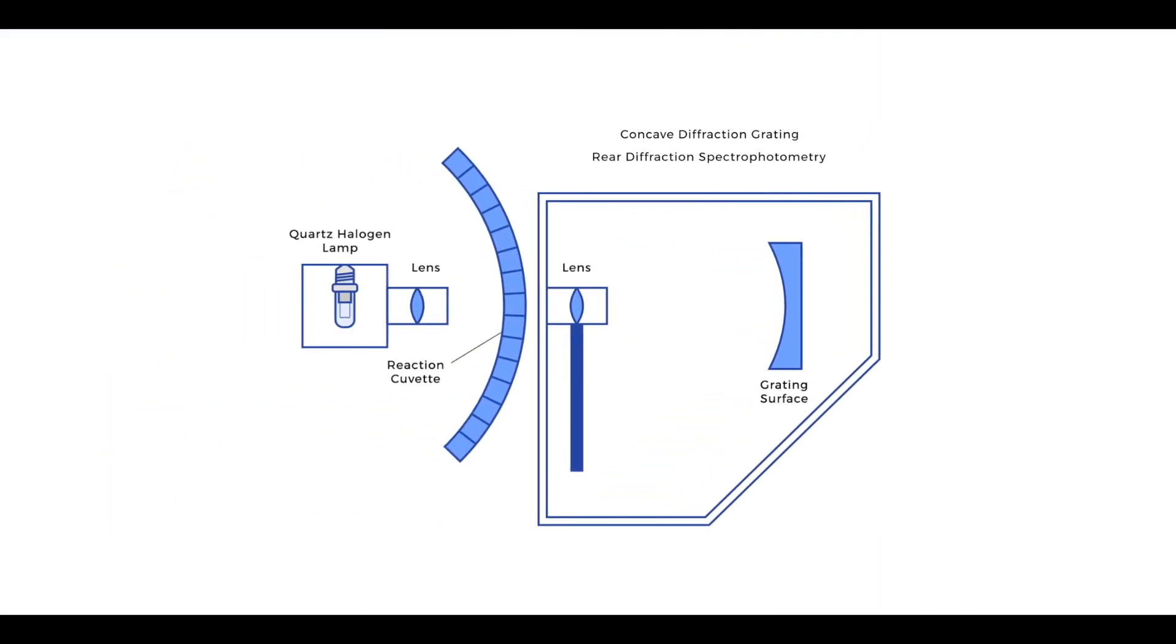The optical system of the TBA-120FR utilizes grating photometry, which provides access to 16 wavelengths ranging from 340 nanometers to 804 nanometers, accommodating a wide array of clinical chemistry tests.